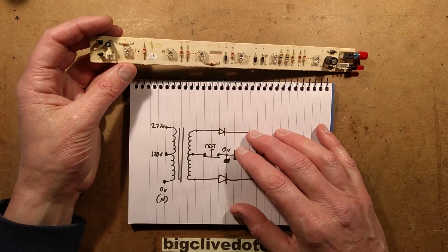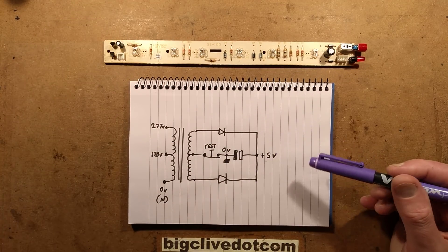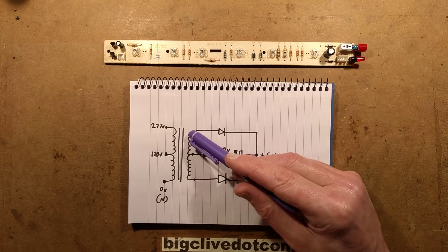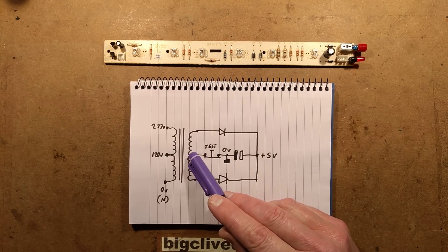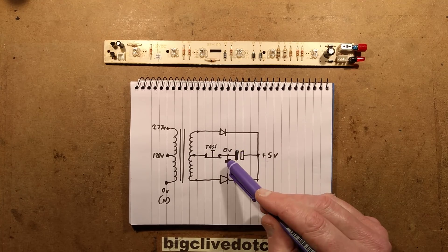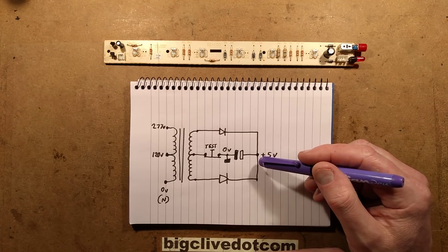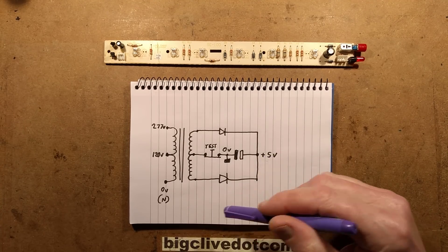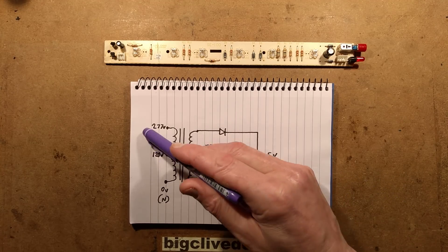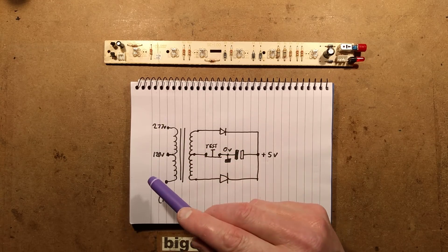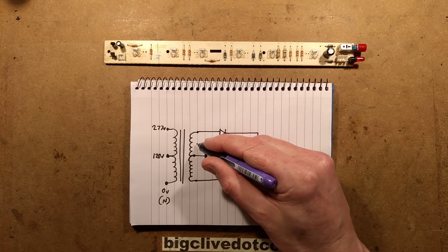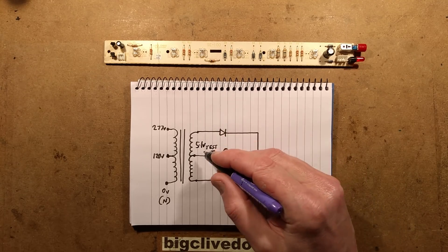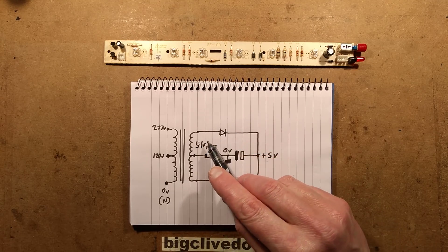We'll break it down into two parts. First is the power supply using a simple rectifier arrangement based on the center tap winding. The middle of the winding is effectively ground. The test button breaks that connection, which kills the output so it comes on in emergency mode. The incoming supply goes through the transformer, you get two 5 volt windings.